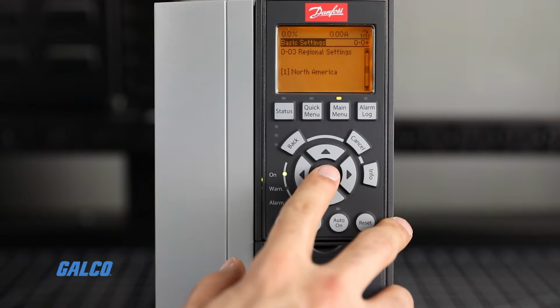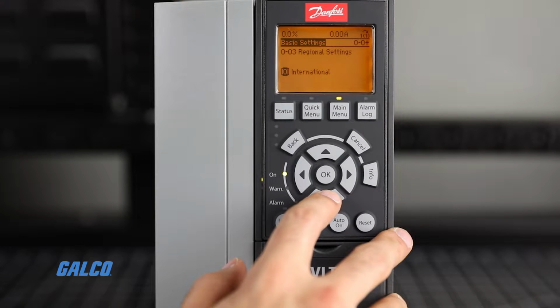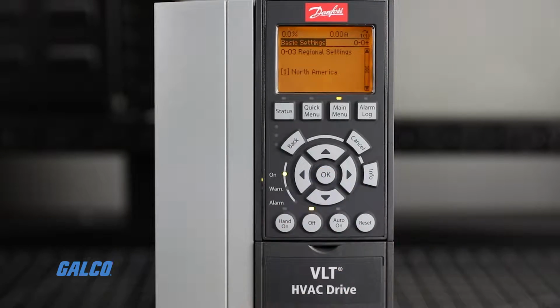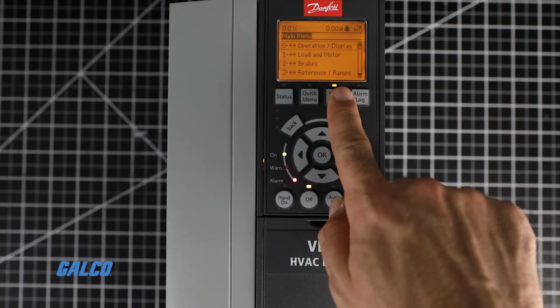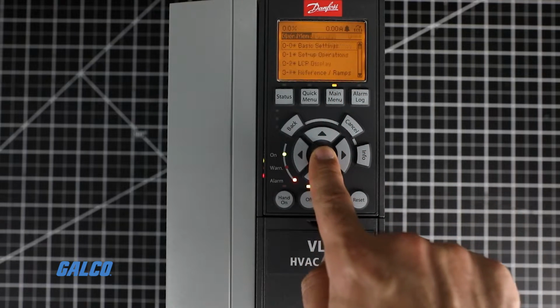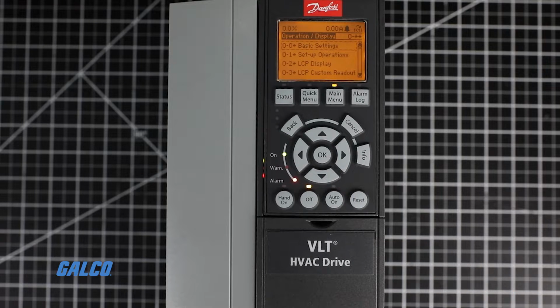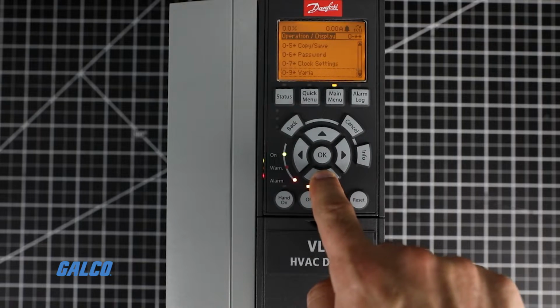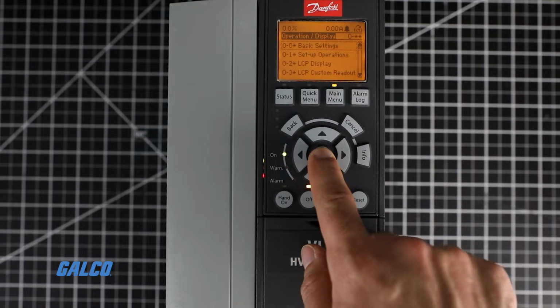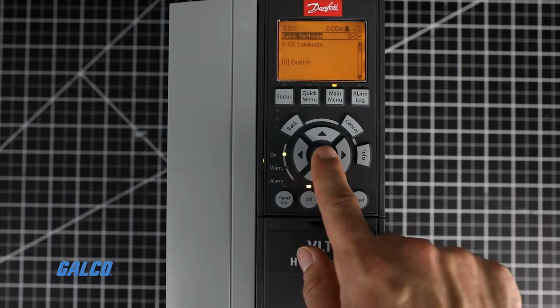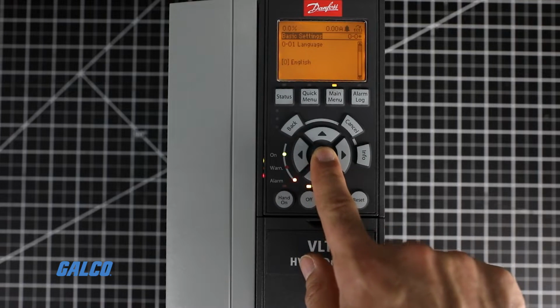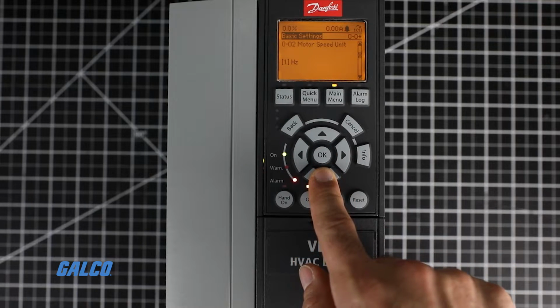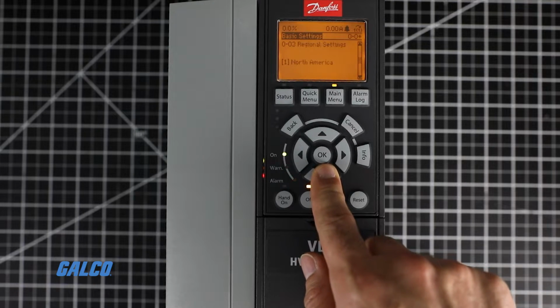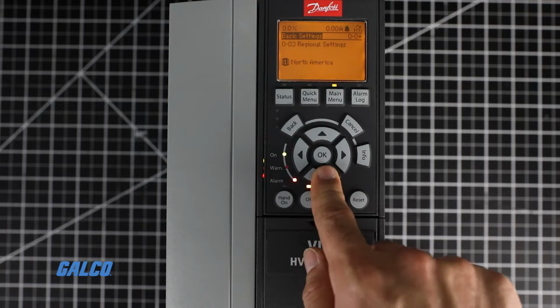To perform a basic startup, ensure that your regional settings match your region. In this demo, we will use the US setting. Press the main menu key. Enter group 0 using the OK key, enter parameter 0-0 basic settings, and then use the arrow keys to select 0-03 regional settings. Press OK to highlight the value, use the arrow keys to find US, the parameter value will equal 1, and press OK to confirm. This puts the drive in North American defaults.